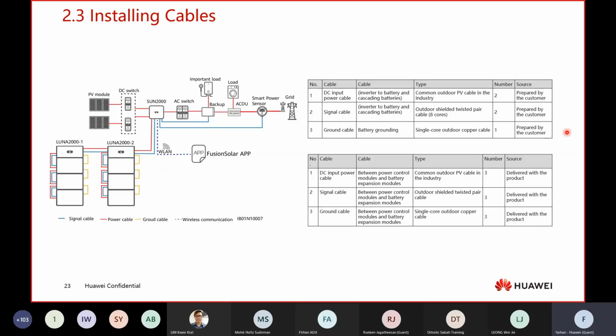Here you can see there are two tables. This one needs to be prepared by the customer, like the DC input power cable, which connects to the inverter. Since we don't know how long the cable needs to be to install the inverter, maybe behind the door or in the same room, the customer needs to prepare this cable from the inverter to the power module. Similarly, the signal cable from the inverter to the power module is prepared by the customer, and so is the ground cable, which connects to the ground point after everything is finished.